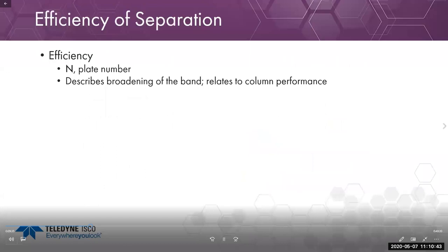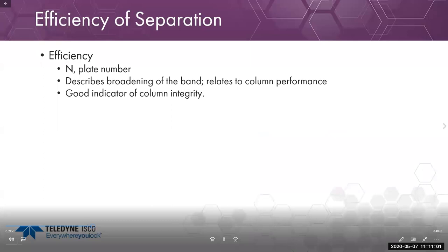The last component of the resolution equation is efficiency. With prep HPLC, we already have greater plate number performance than flash columns because we work with smaller particle sizes. Efficiency effectively describes band broadening and relates to column performance. Efficiency is also a good indicator of column integrity — when you start to see efficiency decrease over time, it usually means you need to change your column or guard column, as the physical characteristics are changing and affecting your chromatography.